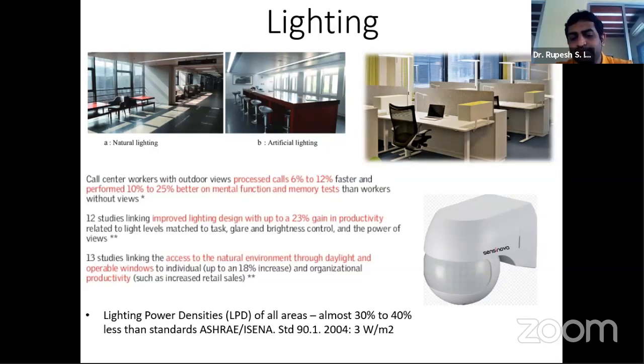So before we used to design almost 10 watts per square meter or 1 watt per square feet, and now that has come down to as low as 0.3 watt per square feet or 3 watt per square meter. So my LPDs would come down when my lighting efficiency would go up. So that would reduce my lighting load requirements also on the electrical side. So my feeders would have lesser cable size. My wires would be of a smaller diameter. So that would again affect my costing on the capex side.